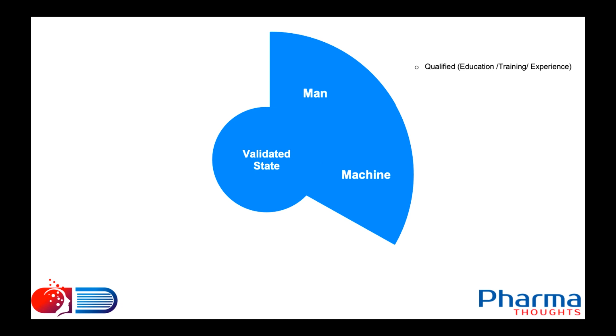Similarly, the second element is machine. All the equipment used for manufacturing or testing shall be appropriately qualified before starting usage. Normally, the important phases of qualification are installation qualification, operational qualification, performance qualification, etc. However, please note that though qualification of equipment is an important part of validation, by only qualifying the equipment we cannot conclude that the process or systems are validated.